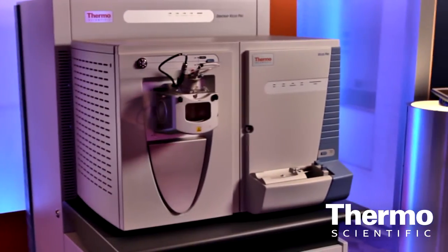So what's the takeaway for customers about this new technology? I think the Velos Pro is a product that goes beyond the traditional ion trap and into new spaces where we've never been before. In your lab, you can now have one instrument that can do quantitation and qualitative workflows. You can do relative peptide quant with TMTs and structural elucidation very quickly in a way that wasn't easily accessible before.